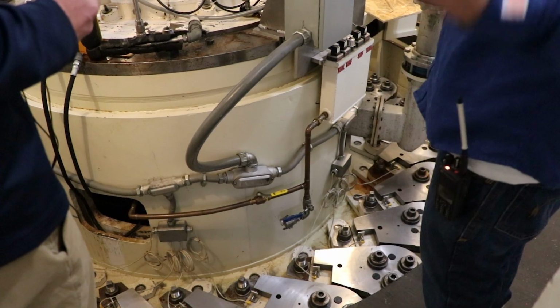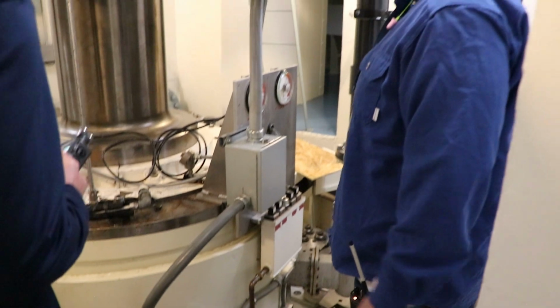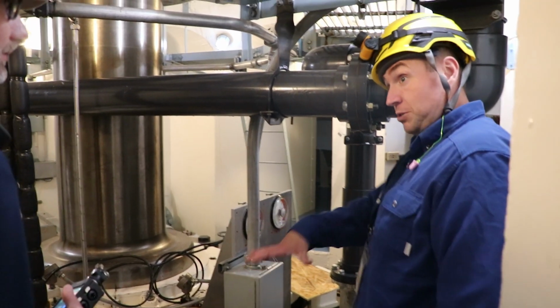The wicket gates around the outside of the turbine, if the governor either automatically, through a response called droop, or if the system calls for an increase in load, they'll open up. They can open slowly as a ramp rate if the system calls for it—you can ramp it up over the course of an hour. Or in the case of droop, if the grid frequency dips and the automatic response built into the governor requires it to open the wicket gates, it can open them to full open in like 12 seconds. And as soon as the water's there and the force is on the wheel, that power is on the grid.